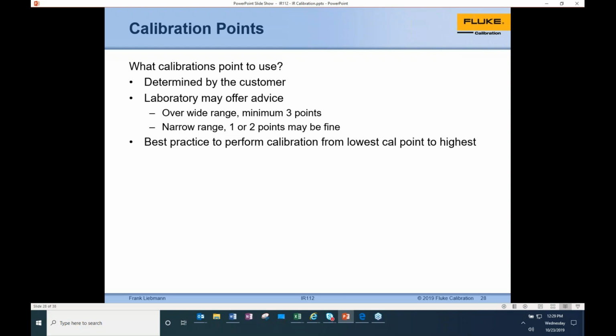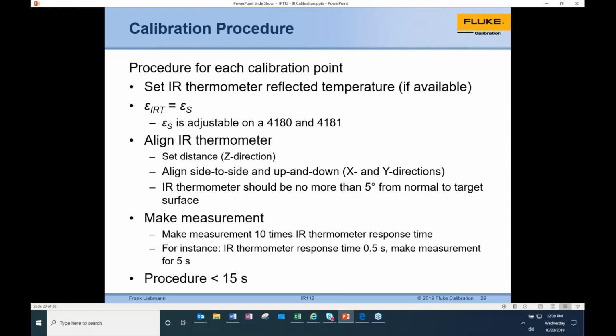With temperature in general, it's always best practice to go from your lowest calibration points to the highest. It just seems to net you the best results. And two, typically with the heat sources, it's usually a much faster process to go from cold to hot versus going very hot down to cold. So when you're setting them up, our targets on the 4180s are calibrated at 0.95. The cool part about these is you can adjust the emissivity. There is a setting based on Planck's law in there where you can set it to say 0.93, 0.92, and it'll correct the target temperature to emit that. Kind of a neat feature there.